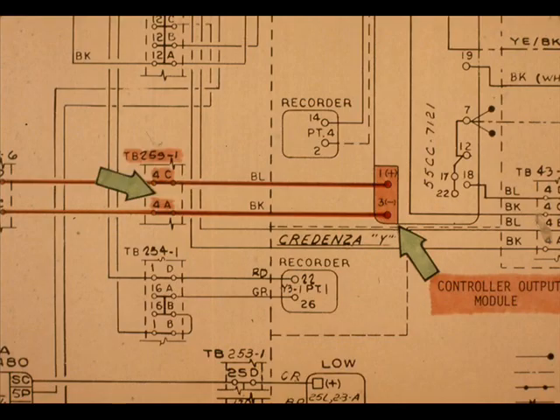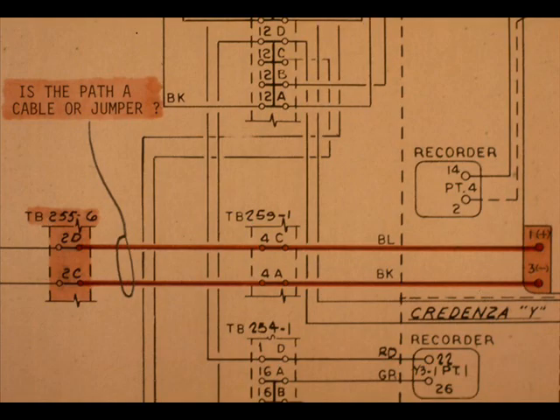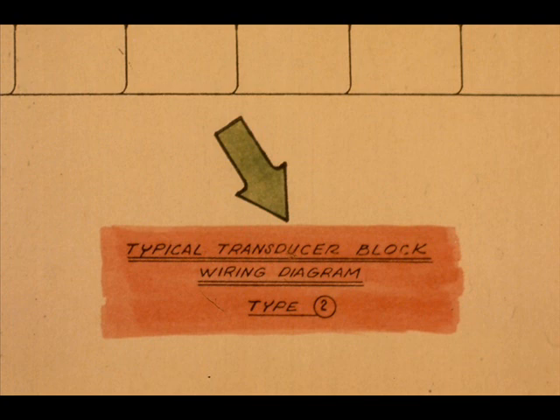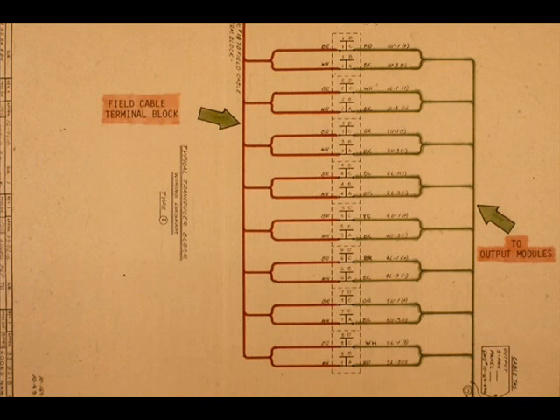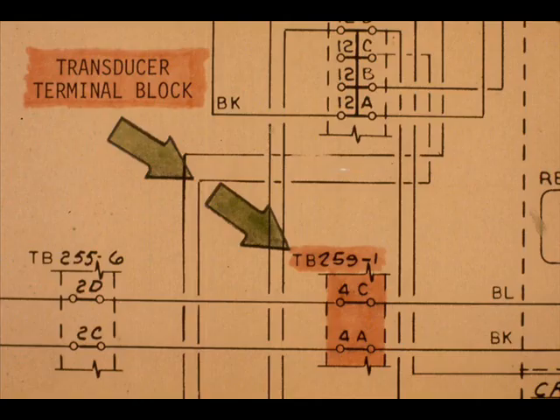Is the path a jumper or cable? You cannot tell by looking at the loop diagram. To find out, we have to look at a transducer block wiring diagram. This is a transducer terminal block, so named because it shows the interconnection between the output module and the field cable terminal block. TB259-1 is a transducer terminal block. The wiring on TB259-1 should conform to the transducer terminal block drawing.